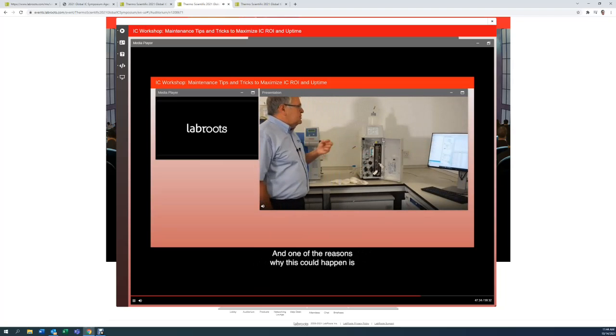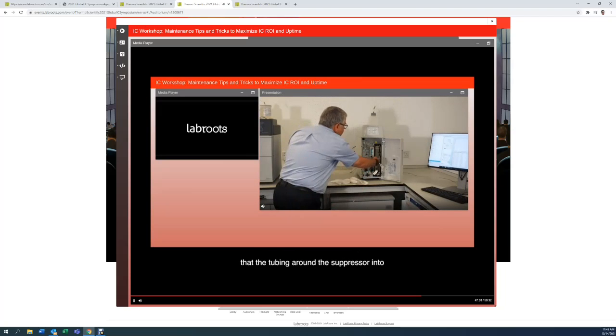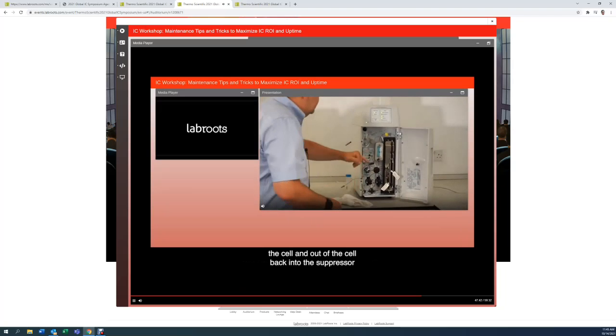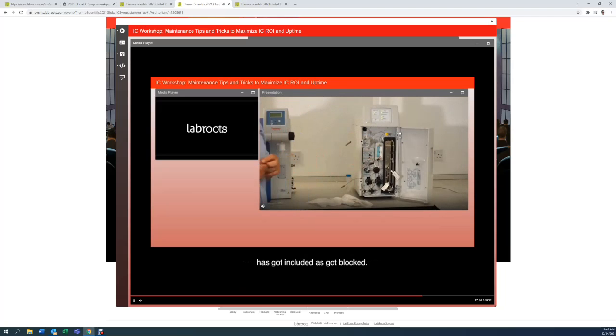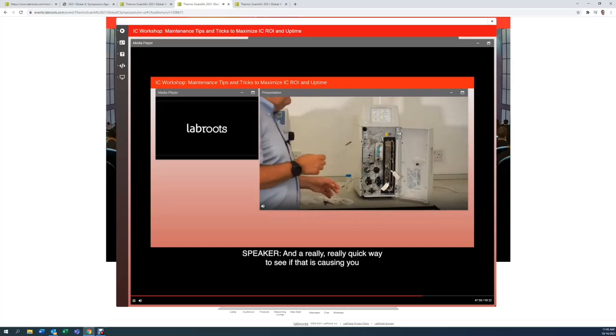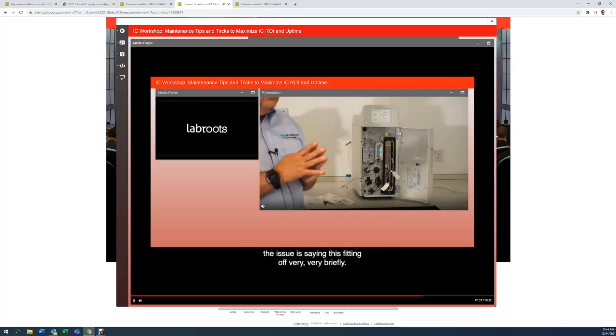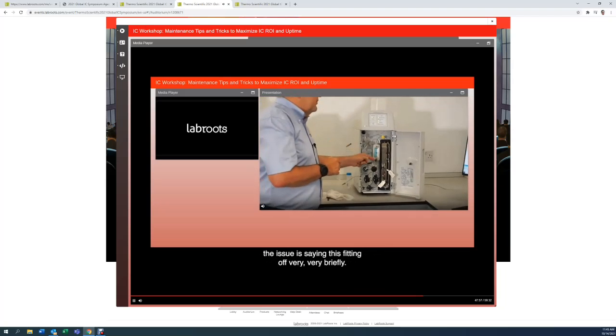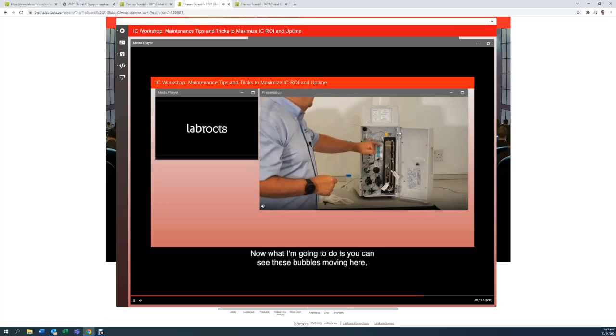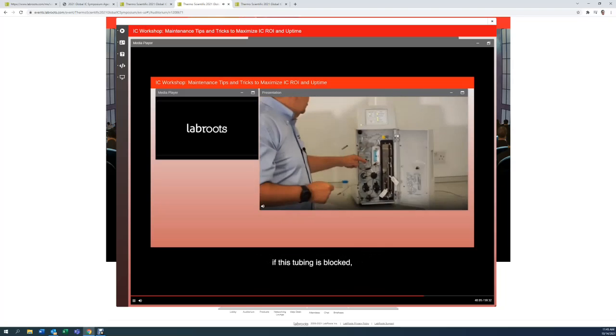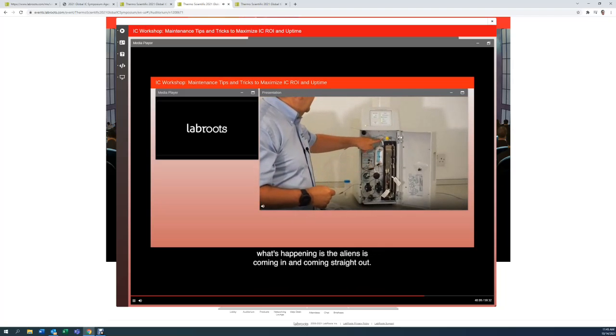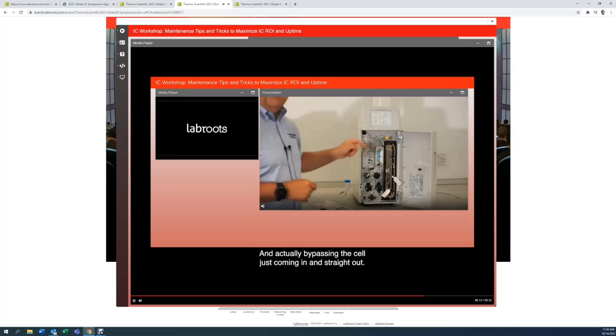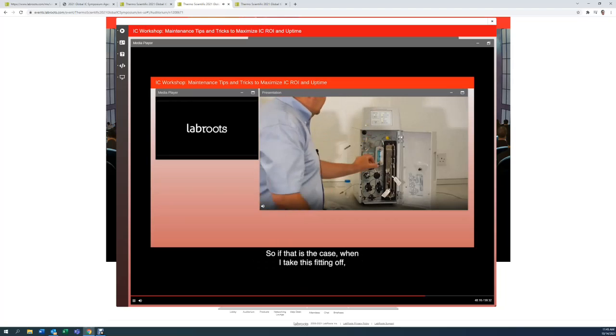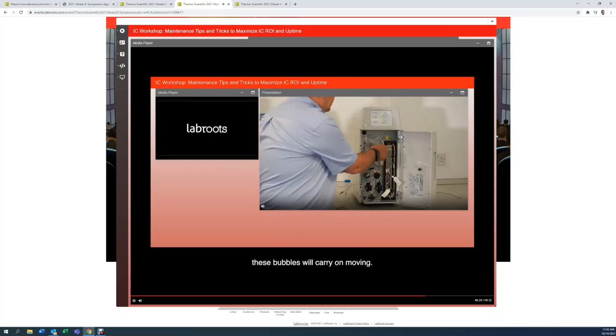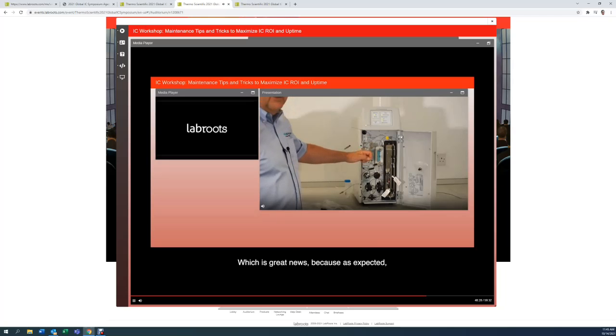And one of the reasons why this could happen is that the tubing around the suppressor into the cell and out of the cell back into the suppressor has got blocked. And a really, really quick way to see if that is causing you the issue is take this fitting off very, very briefly. Now what I'm going to do is, you can see these bubbles moving here. If this tubing is blocked, what's happening is the eluent is coming in and coming straight out, and actually bypassing the cell. It's just coming in and straight out. So if that is the case, when I take this fitting off, these bubbles will carry on moving. And the bubbles have stopped, which is great news, because as expected, there is actually nothing wrong with this instrument.